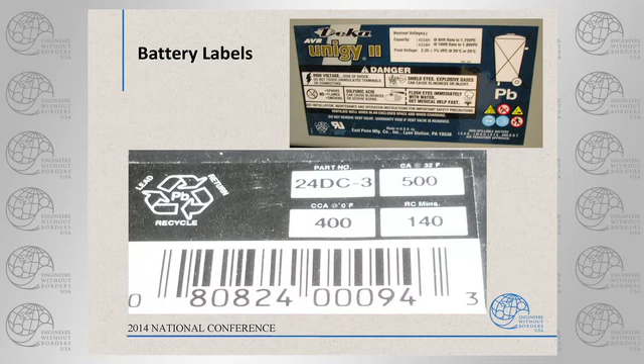Other things, float voltage. It says you want to float this battery at 2.25 plus or minus 1% volt per cell at 25 or 20 C. And you go, it ain't that cold where I am. Well, then go back to the manufacturer's catalog and find out what the volt per cell needs to be at the temperature you're likely to encounter. Right.